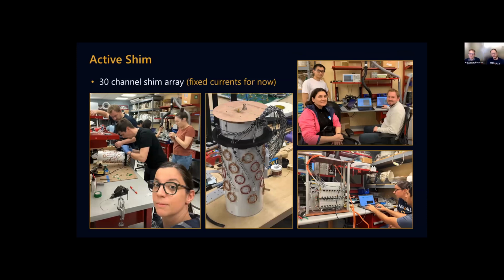The other field homogenization scheme that we devised was using active shimming. We wanted this to be a little bit of a novel twist on ultra low field. Typically, one of the limitations, as we know, in ultra low field is the homogenization of the field. And in simulation, we proved to ourselves that using active shimming could improve the homogeneity quite a bit. So starting from about 3,000 ppm, you would reduce your inhomogeneity to maybe 100 or so ppm. That would allow you to do gradient echo imaging possibly. This is still an area of research, so I'm not going to show further results for this. This is where we're working on that.